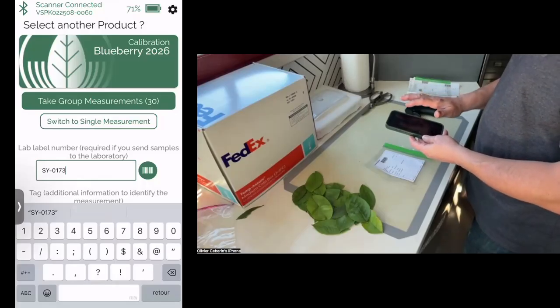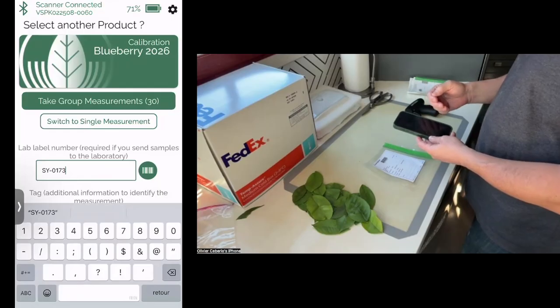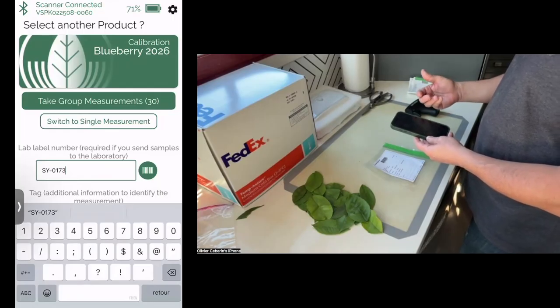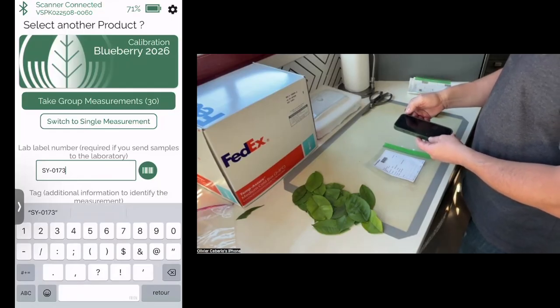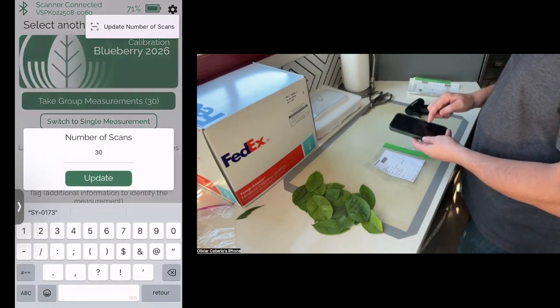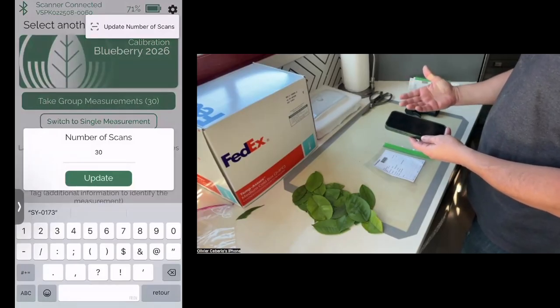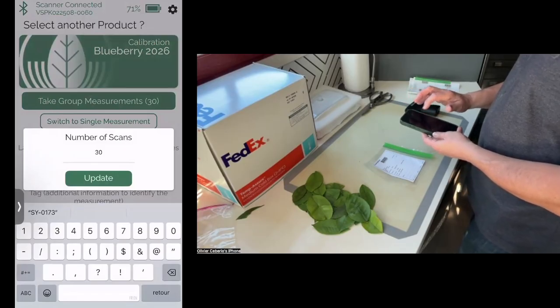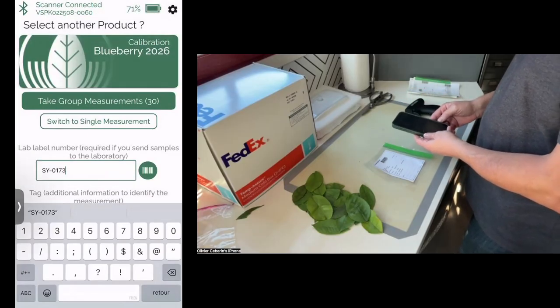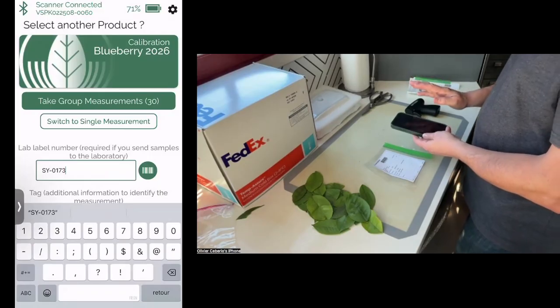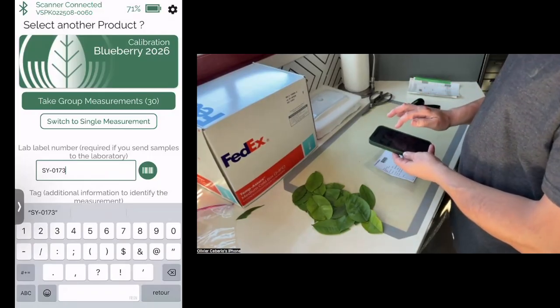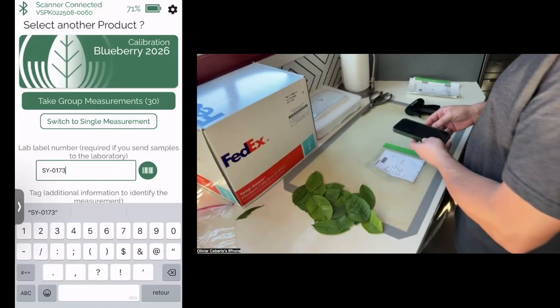You have to be careful first with the scan number. So you see take group measurement, there is 30. It means that the scanner is expecting 30 leaves for this specific group measurement. If for another calibration, you need to change that number, then you press on the gear and you can update that number. So if for another crop than blueberry, we'll need only 20 leaves, you will have to update to 20 leaves. But we will have a chance to repeat that many times before it starts. So I update. So now you're ready to scan. You have to be careful, because if you press take group measurement, it will immediately start a scan. So that's not what you want.